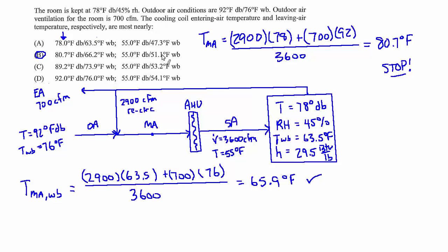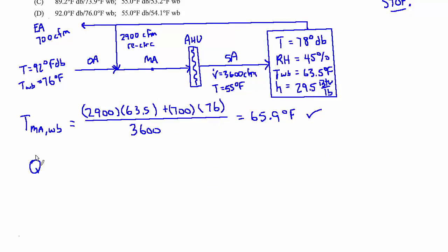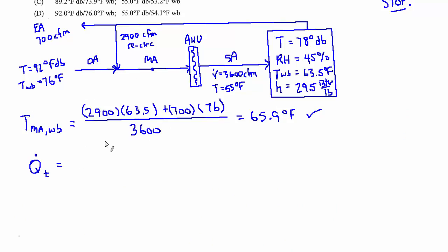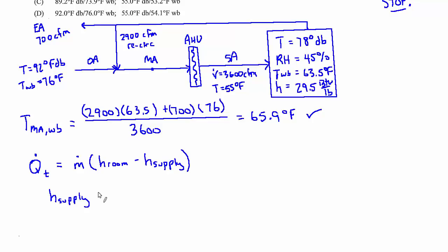Now to find the wet bulb temperature of the discharge air off the coil — the air supplying the room. We were given the sensible and latent heat loads, giving a total load of 130,000 BTU per hour. We can write: total cooling load = ṁ × ΔH, where ΔH is the difference in enthalpy between the room air and the supply air. Rearranging to solve for the enthalpy of the supply: H_supply = H_room − Q_total ÷ ṁ.